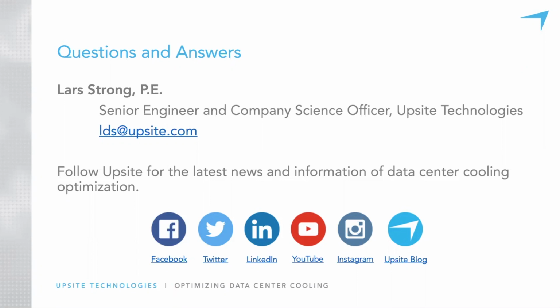Okay, so the next one is, how close in efficiency can we get to liquid cooling with an airflow optimized data center? That's a good question, and I don't know that I can give you a number. There are so many variables involved, and one of them relates to the tier level of the infrastructure. If it is, say, a tier 4, taking the extreme example, a tier 4 fault tolerant infrastructure with dual concurrently maintainable electrical and mechanical distributions, then it's going to be inherently less efficient. And then there's the environmental factor. If the facility is sitting in the northern US, or down in Arizona, that is going to have a huge effect.